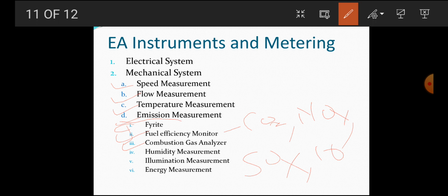Specific sensors are sealed inside the equipment that can be changed to measure a particular gas. And the gas analyzer has two probe connections, so two gases can be measured simultaneously. So this is our combustion gas analyzer.